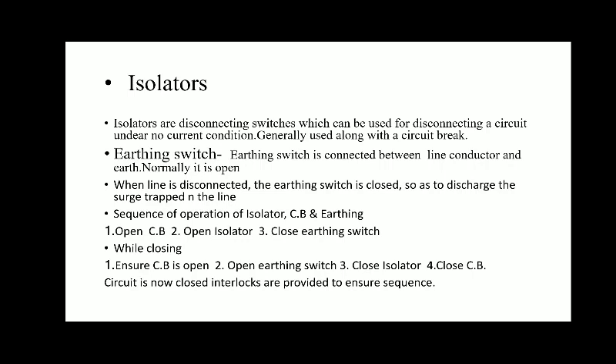Okay, when there is no current, or there is an absence of current in your circuit or in your line, this is an isolator. Next, the most important thing used in your line is the earthing switch. The earthing switch is connected between the line conductor and earth. Normally it is open, but when the line is disconnected, the earthing switch is closed so as to discharge all the charge, all the surge trapped on the line capacitance, to the earth. Now the earthing switches are mounted on the frame of an isolator.